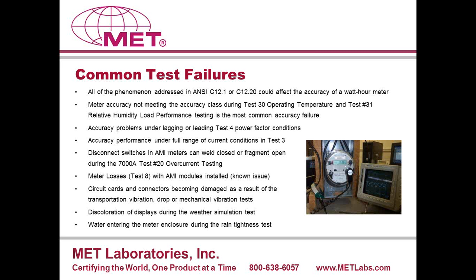The disconnect switches, lots of times we'll see issues with that. Although the manufacturers of the disconnect switches do seem to be getting better, the problems we'll see are typically welding shut of the contactors, where we can no longer actuate that disconnect switch after the 7,000 amp peak test, which is a test where you've got to continue to operate both before and after those tests. We'll see sometimes welding with contact there, or even some fragmentation. There's also another part of that overcurrent testing that goes beyond. It's more of a hazardous test. But there you're looking to make sure that the product fails safely. But in terms of failures, most of the time you're going to see that failure occur at the lower current where it doesn't actuate that disconnect any longer.